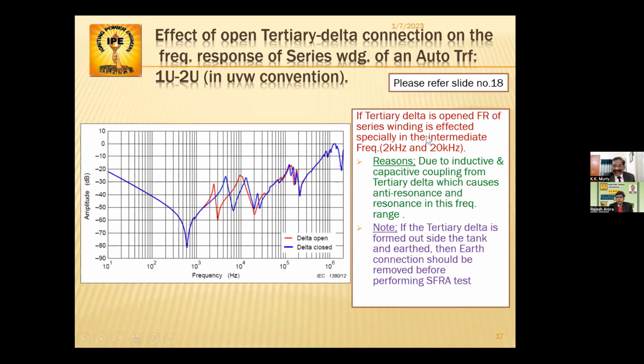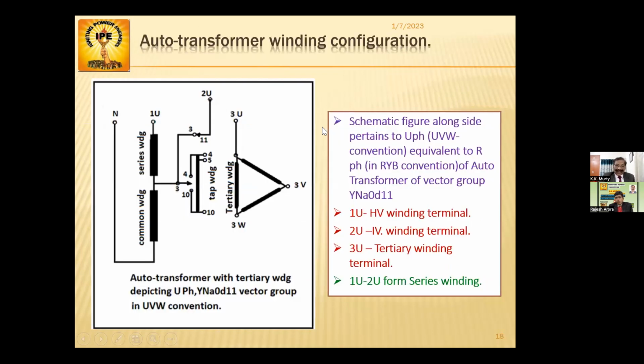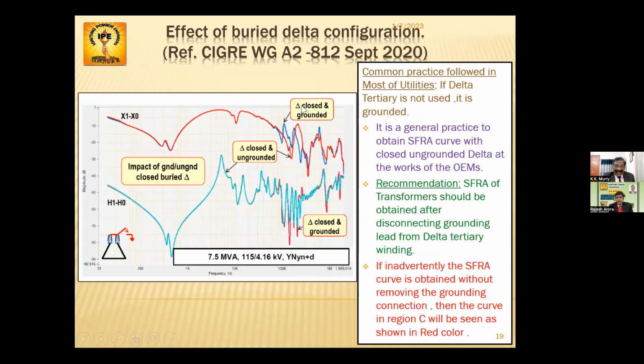You can see that the series winding is affected, especially in the intermediate frequency, that is 2 kilohertz to 20 kilohertz. And this is, of course, when the delta is closed and ungrounded, and when the delta is closed and grounded.